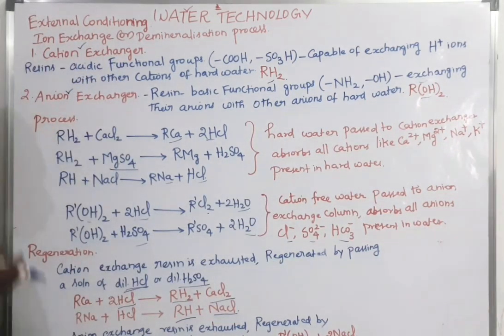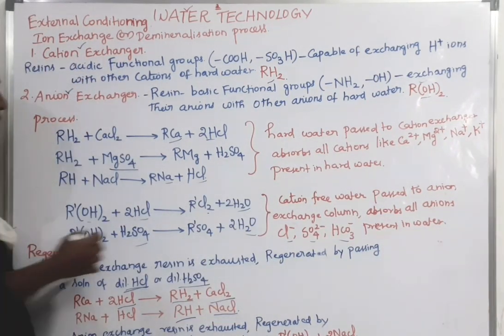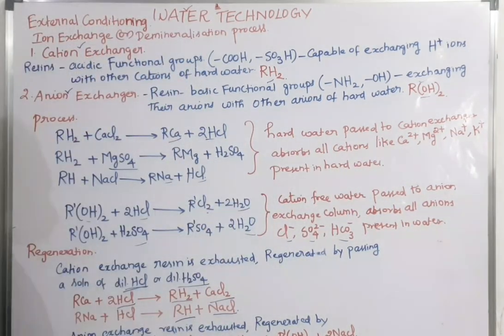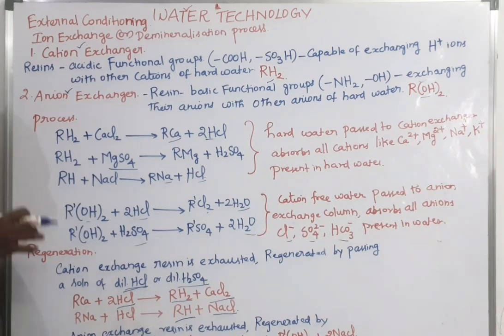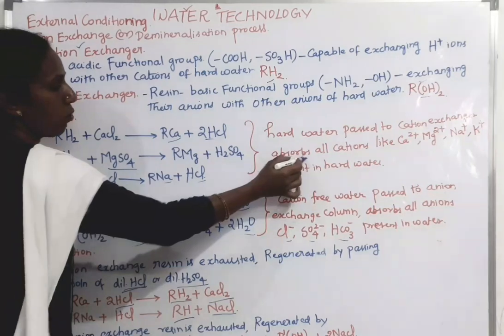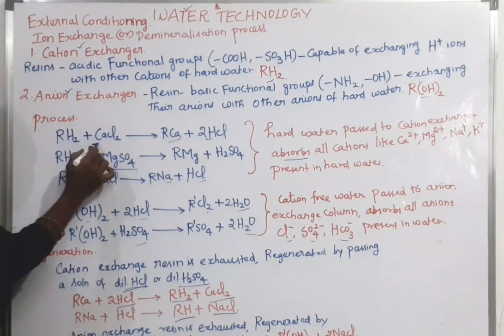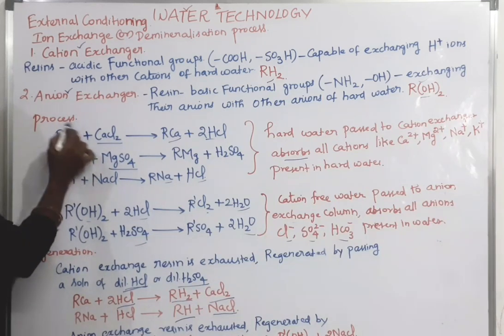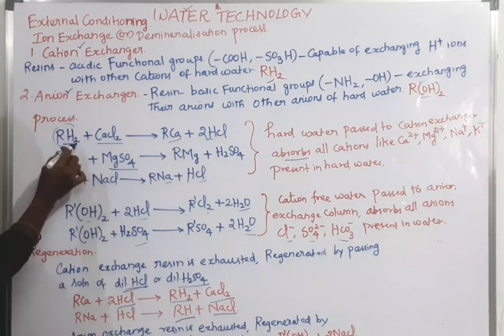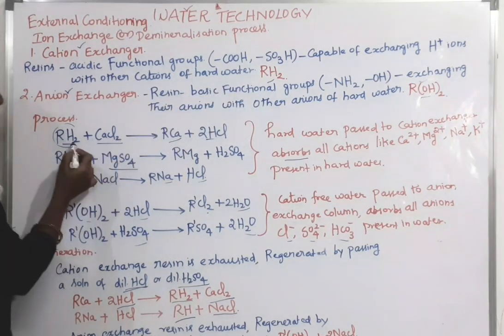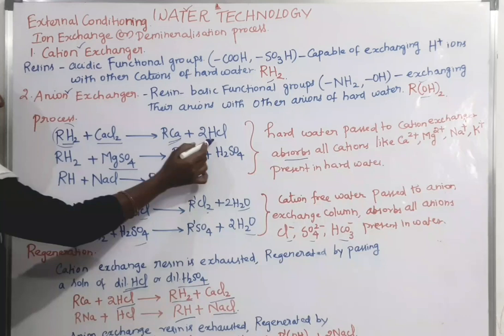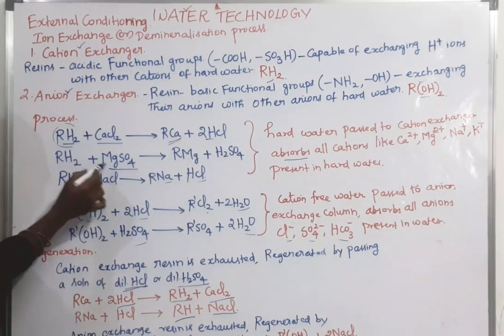Let us see the process. The hard water is first passed into the cation exchanger, which absorbs all the cations like calcium, magnesium, sodium, and potassium present in the hard water. The reaction is: calcium chloride plus RH2 gives R·Ca plus 2HCl. This is the general representation of the cation exchanger RH2, which absorbs all the cations.